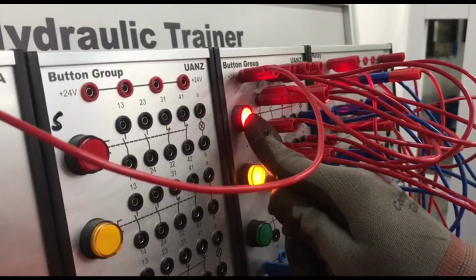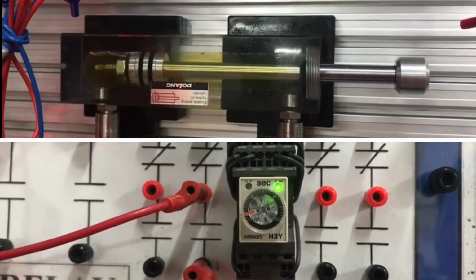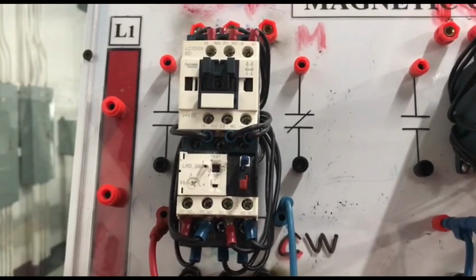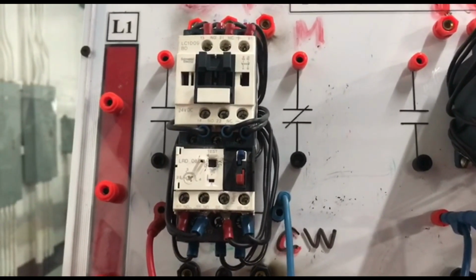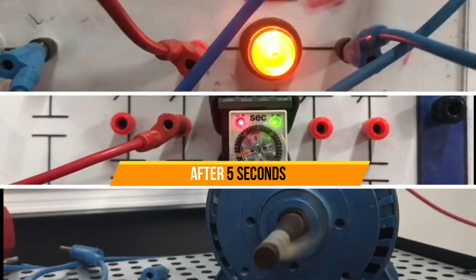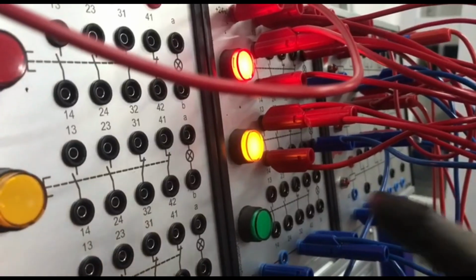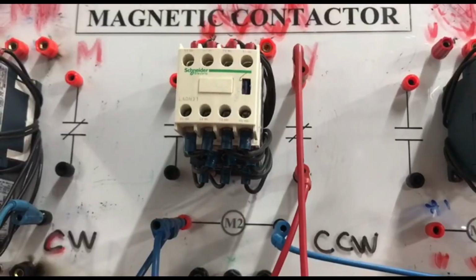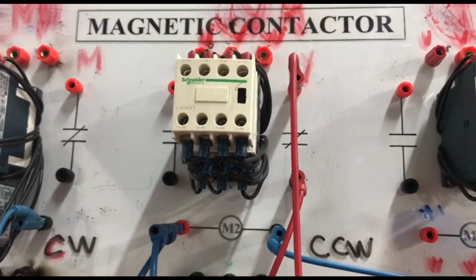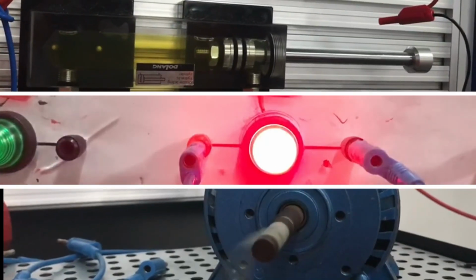When push button 1 is pressed, the hydraulic actuator will push the ramp outward, and while holding the push button, after 5 seconds, the hydraulic motor will rotate clockwise to lower the ramp. When push button 2 is pressed, the hydraulic motor will rotate counterclockwise to hoist the ramp together with the retraction of the hydraulic actuator.